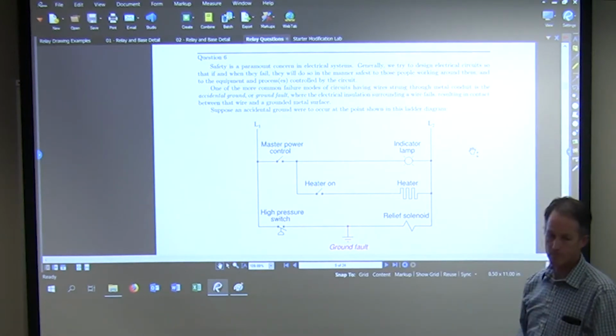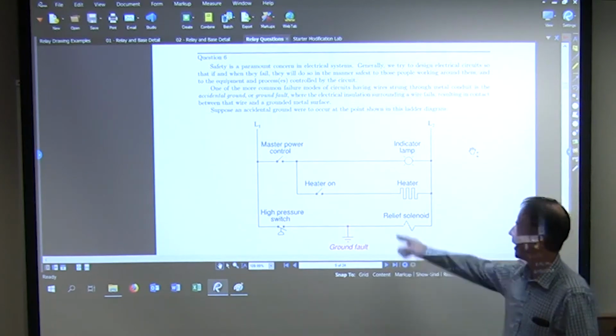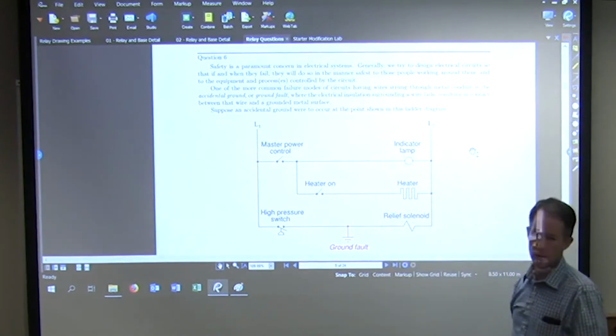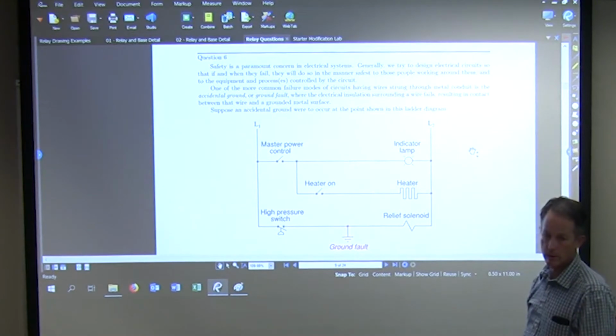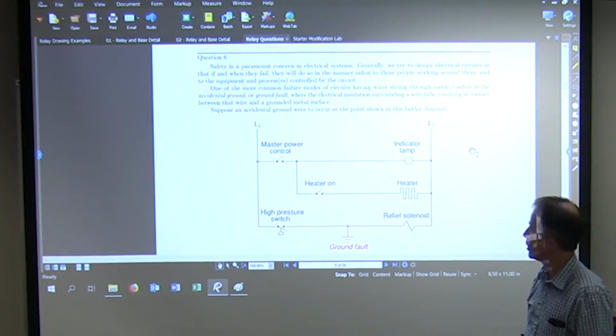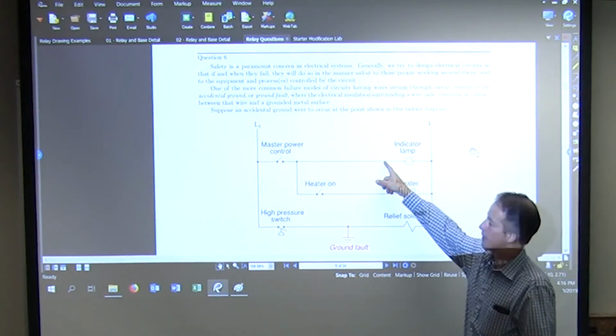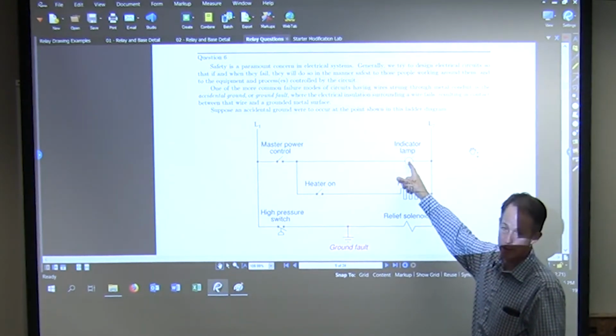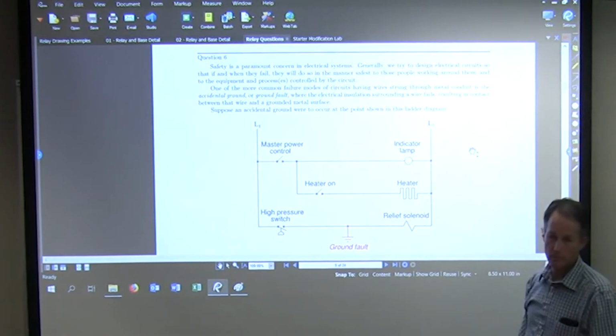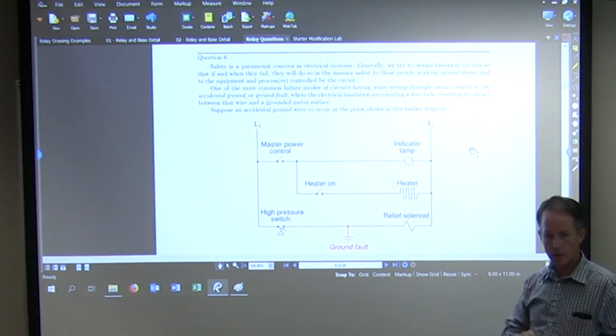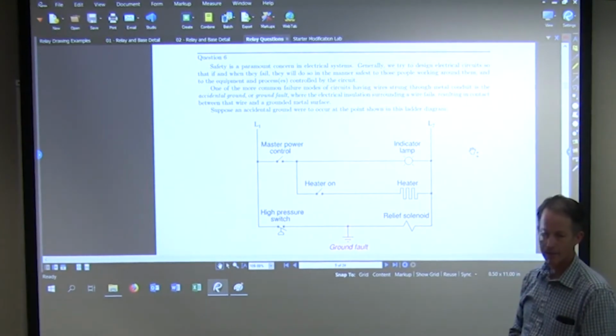But if you put that sense to ground and trip fault it to the light, yeah it would trip. It doesn't have enough resistance like the solenoid does. But if you had a 110 solenoid and it was the other way around, if you had this fault here with that light there, it would not trip, because of the resistance. It's going to act like it's a 110 circuit, because it's using the ground.